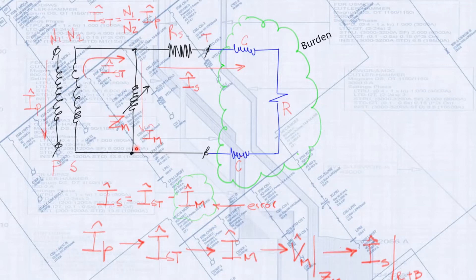The cable leads and relays wired to the CT are generally referred to as the burden. Once current flows through the primary circuit, the CT drives a secondary current through the burden and secondary winding. This is the current that the relays sense and operate upon. The relay current IS is thus the ideal total secondary current IST less the magnetizing current IM. The magnetizing current is thus an error to the relay current. The simplest way to summarize how all of this comes together is this way.